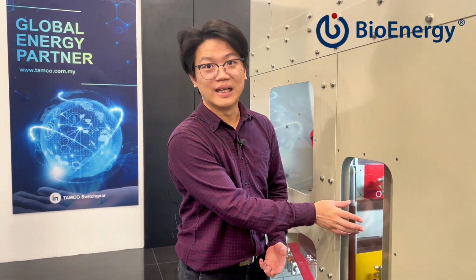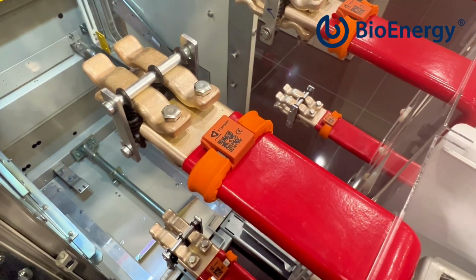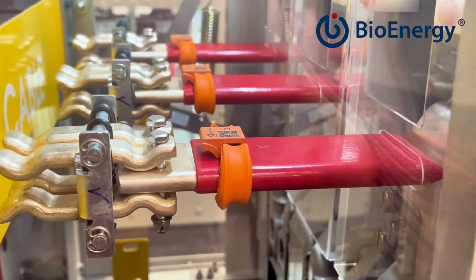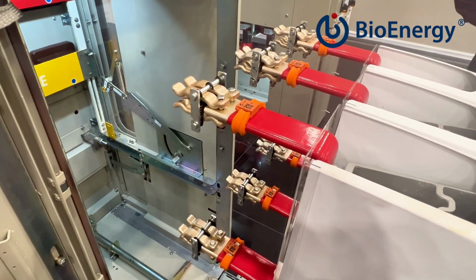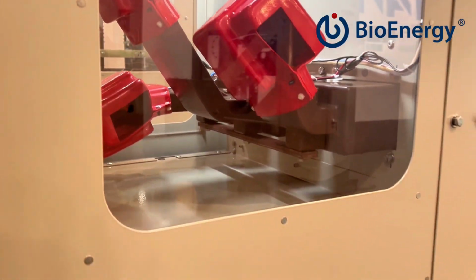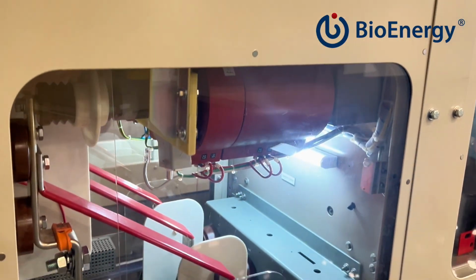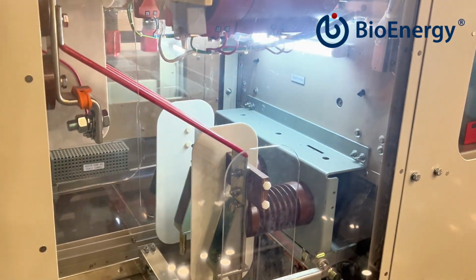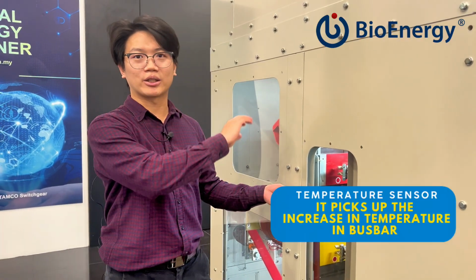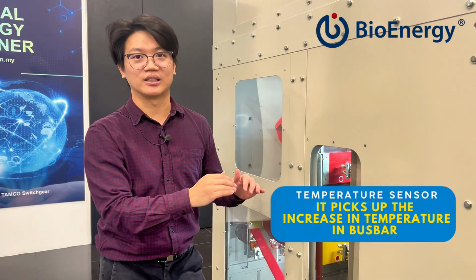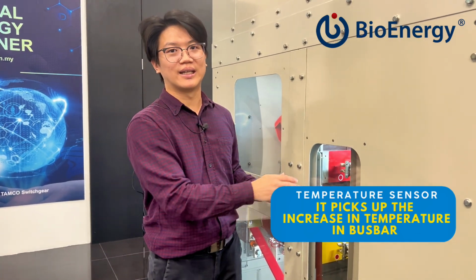So we actually install temperature sensors. Temperature sensors are located in parts of the switchgears. So these temperature sensors will pick up the temperature increases in the busbar. So all these temperature increases in the busbar are sent back to the HMI. And if there is any abnormal temperature, then the HMI should give you a pre-alarm and an alarm.